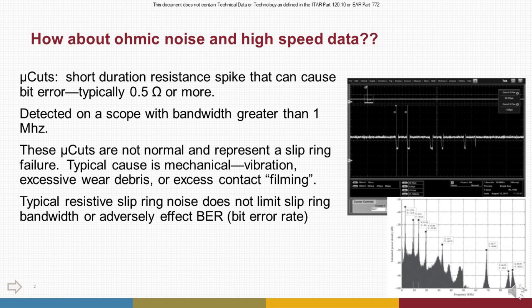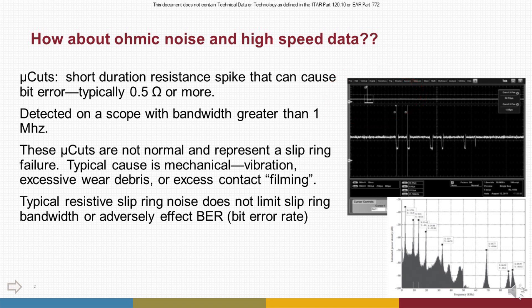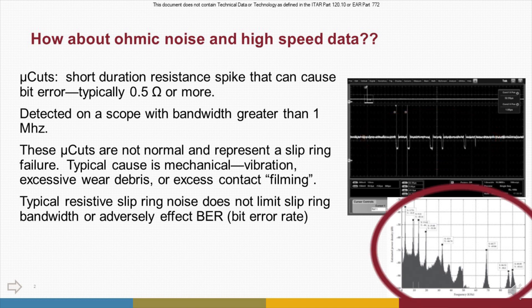Typical causes are mechanical or chemical, such as vibration, excessive wear debris, excess contact filming, or plating failures. The oscilloscope trace here shows a typical microcut event. The top trace shows high resistance signal spikes over one ohm, and that is spread out in the middle trace into three pairs of 30 kilohertz spikes, with some obvious attenuation as we progress. This shows that mechanical vibration — with 30 kilohertz as the fundamental — is often part of the explanation of these microcuts.